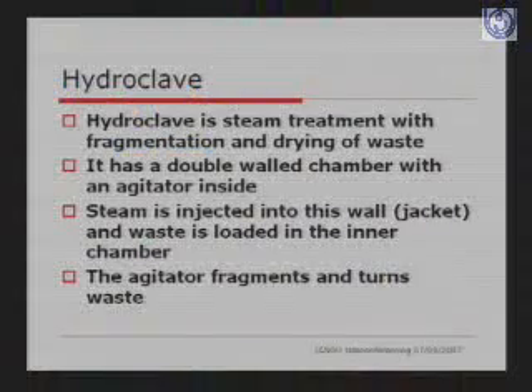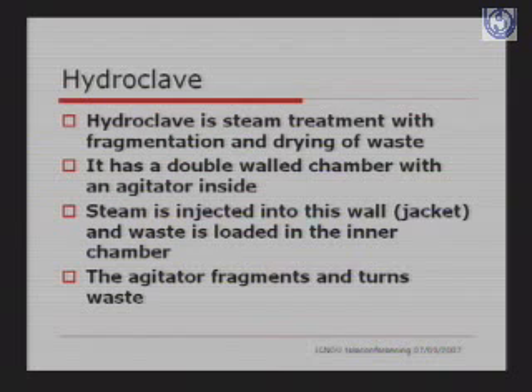Can we have a slide, please? The hydroclave is a steam treatment with fragmentation and drying of waste. Here, what happens is basically there's a double chamber. It's an advanced autoclave. As I said, the steam is not directly in touch with the waste. It's in the outer chamber that the steam keeps moving around, and the waste is inside an inner chamber where it touches the steam and gets disinfected. The steam is injected into this wall, the outer jacket of the double chamber, and the waste is loaded in the inner chamber.